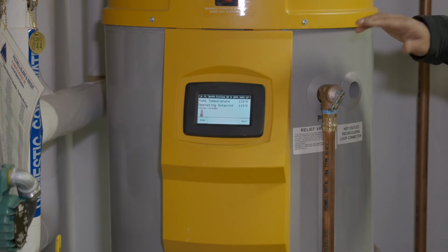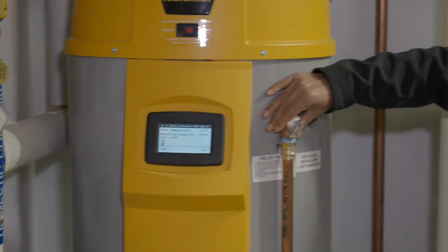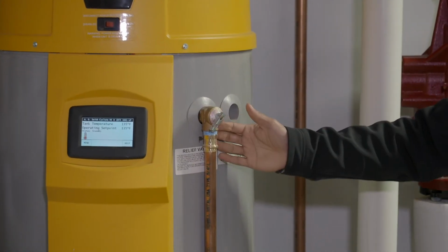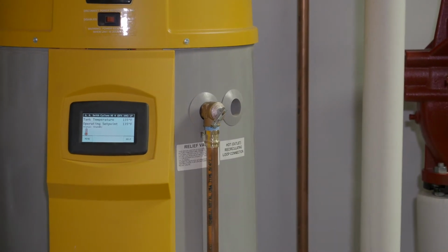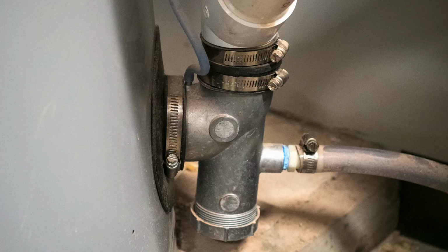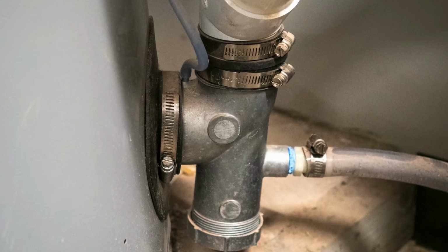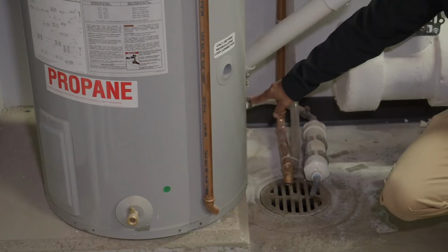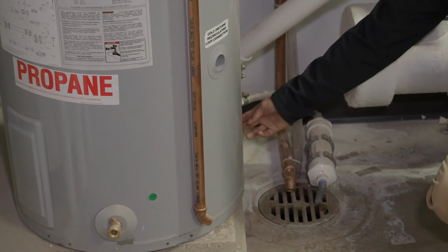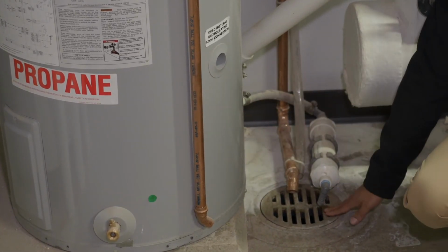Other than that, we have a couple of things here. We have your T&P relief valve here. Make sure that's always free and clear. You have your condensate elbow here. Make sure this condensate is free and clear for periodic maintenance. You have a clean out back down here. Just make sure this is free and clear here.